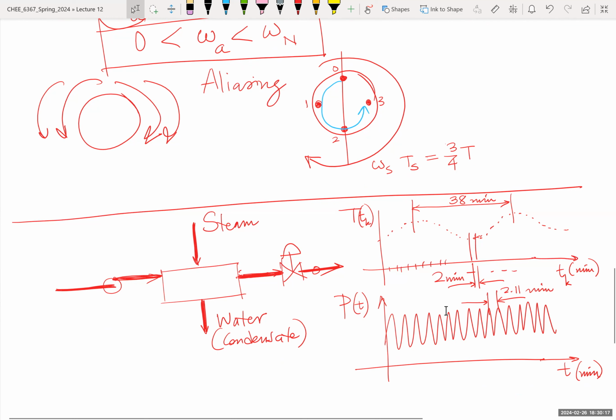Well, I'm trying to understand why I'm getting these oscillations in pressure. These oscillations in pressure suggest that there's something wrong with the valve here. The stem has dead space and doesn't fit very well, so it chatters. The valve goes up, down, up, down, up, down. And every two minutes — that's the reason the pressure I see here continuously changing with a 2.11 minute period is likely due to that flutter in the stem of the valve.